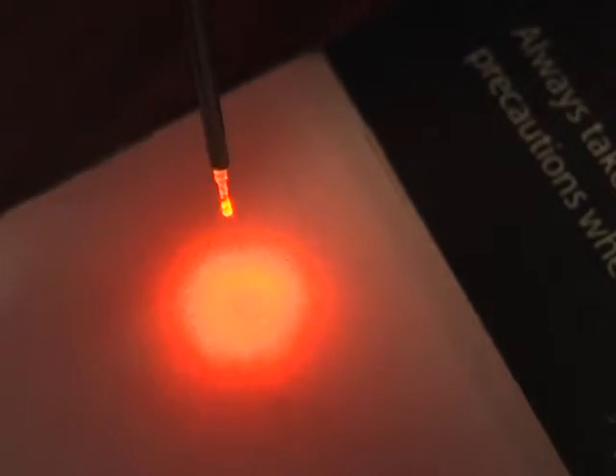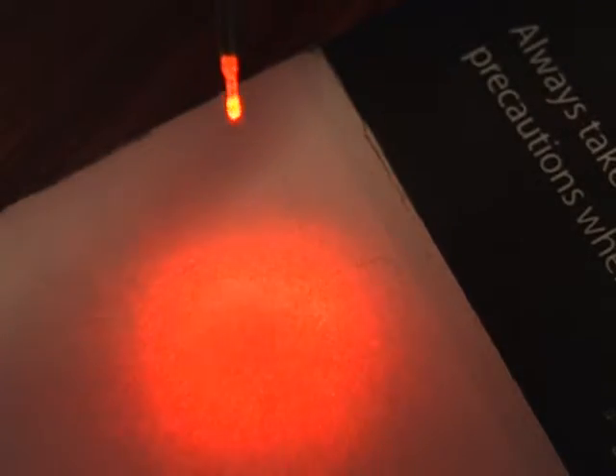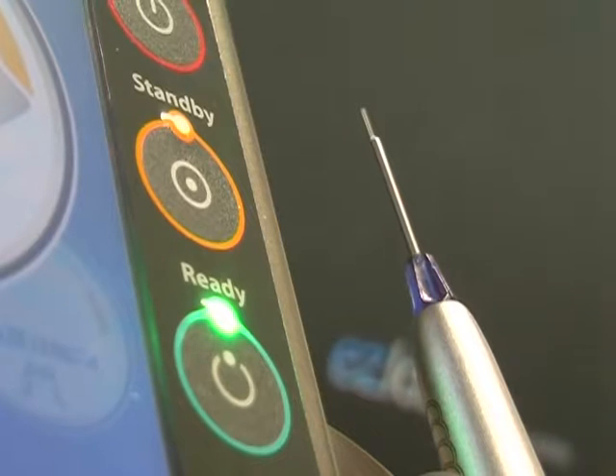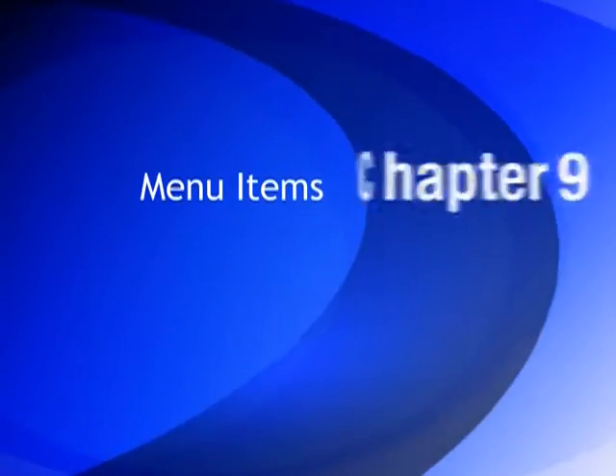After you have initiated a tip, the red aiming beam will of course no longer produce the annulus pattern because of the optical disruption on the end of the tip. Instead, the end of the tip will glow a red color. If this is a distraction, the intensity of the aiming beam may be reduced as shown in the advanced features in Chapter 9.